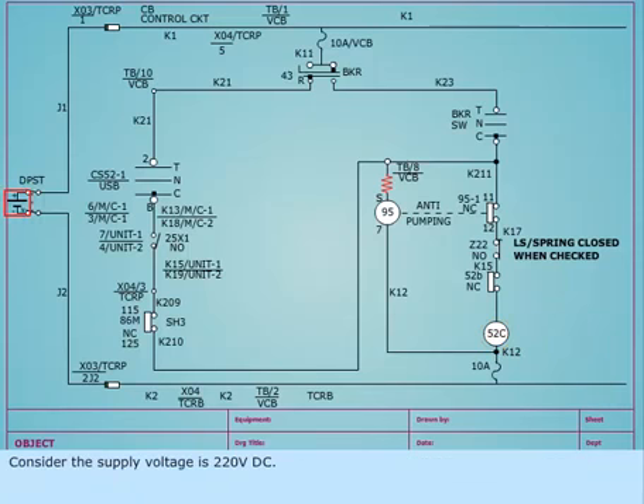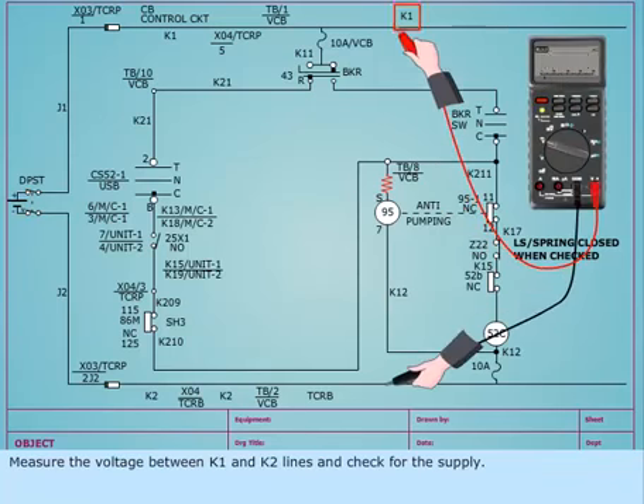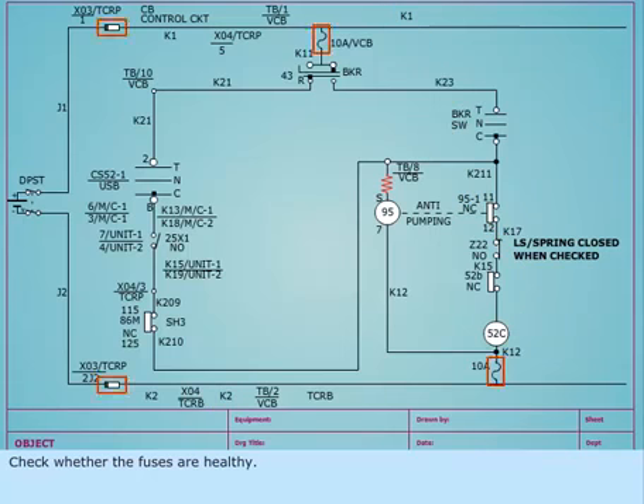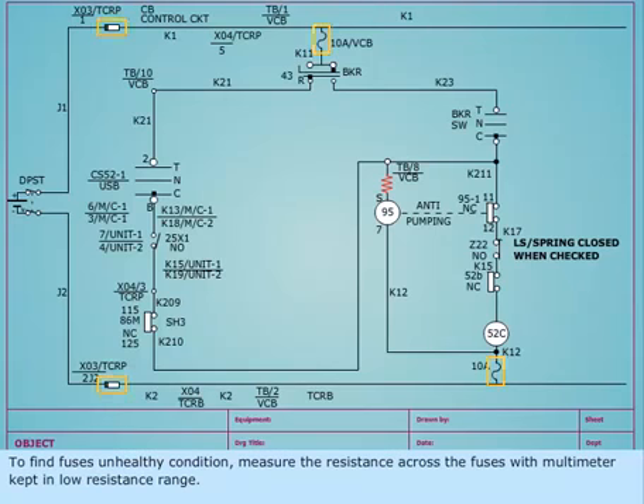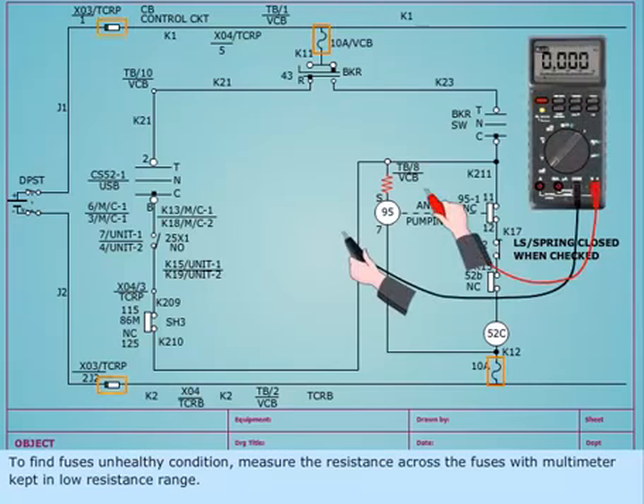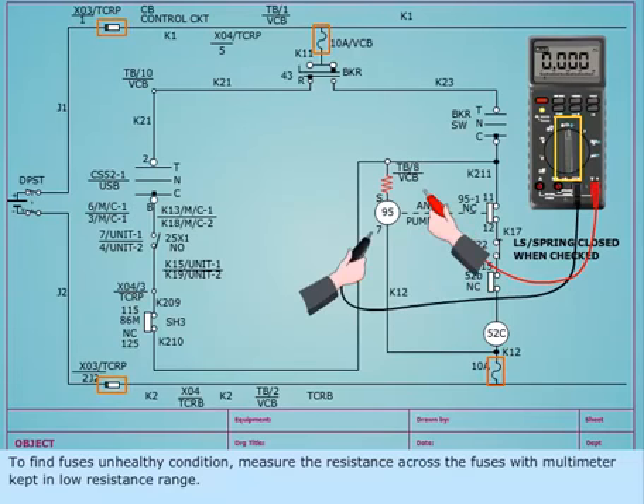Consider the supply voltage is 220 volt DC. Measure the voltage between K1 and K2 lines and check for the supply. Check whether the fuses are healthy. To find fuses unhealthy condition, measure the resistance across the fuses with multimeter kept in low resistance range.